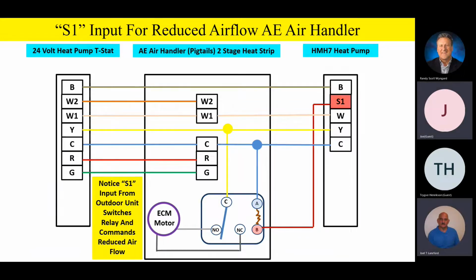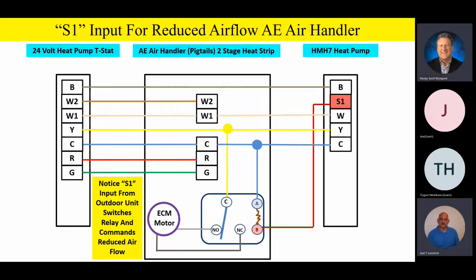So do you have to get this kit for every one of these heat pumps we sell? Absolutely. Thank you. That's an excellent question. The reduced airflow capacity on the indoor unit is going to be switched by that little relay kit. Now, for convenience, we build these kits up for you with a bi-flow filter dryer, some pre-wired pigtails, and the little single pole double throw relay, and so on.